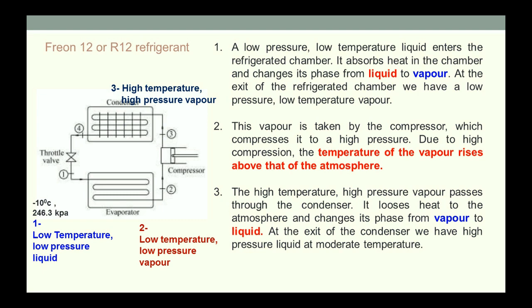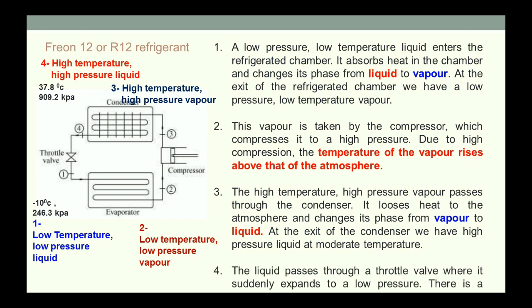When high temperature, high pressure vapor passes through the condenser, it converts back into liquid, but it will be at high temperature and high pressure, normally 37.8 degrees centigrade, approximately room temperature, and pressure of 909.2 kilopascal. This condition is not suitable to send to the evaporator to absorb heat from the surroundings. So we pass it through the throttle valve where the temperature and pressure of the refrigerant is lowered.